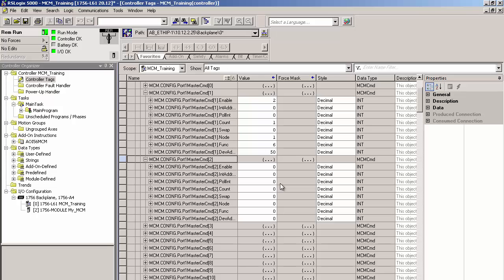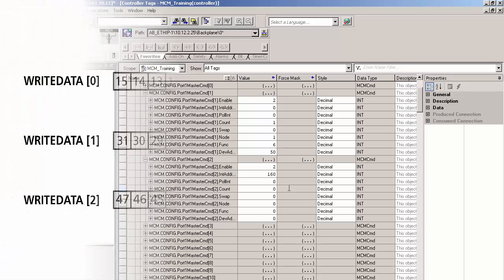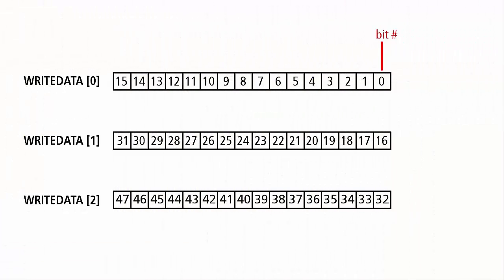Next, I'll expand MCM.config.port1 master command 2. This will be a command to write some bits that will reset the minimum and maximum voltage readings. Under enable, I'll type a 2 so the command runs conditionally. I'll enter an internal address of 160 for return data placement in the database. Now, for the MCM module, anytime you're dealing with a coil or bit level Modbus function code, the internal address for that command must be to the bit level as well.